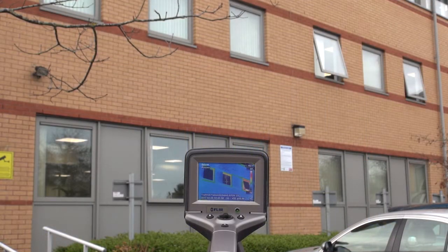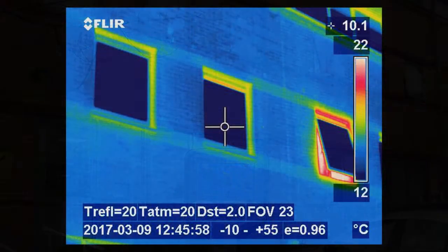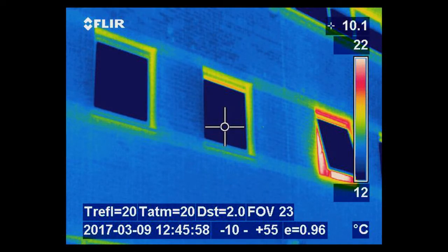This image tells us about the quality of the build. Now you can ignore the colour of the windows, they're not actually cold, that's due to the glass's emissivity. However, you can see that heat is escaping from the frame around that glass, particularly where the window is open at the far end. Also, you can see some other form of thermal heat loss, manifesting as two bands running along the top or bottom of the windows. This is down to some sort of internal thermal bridging.